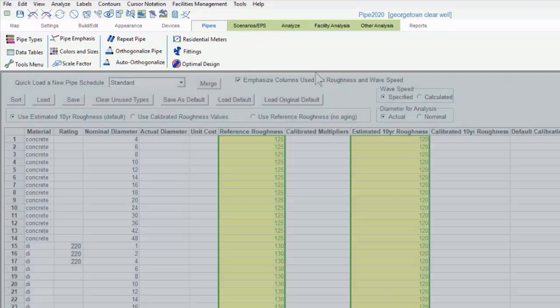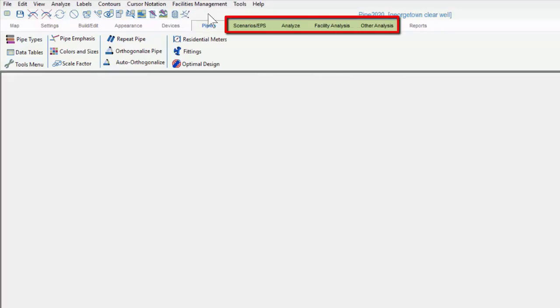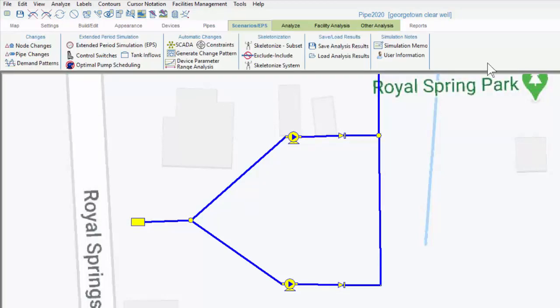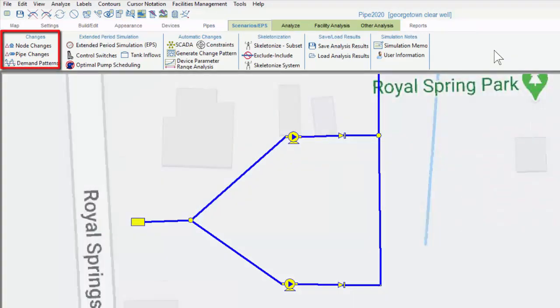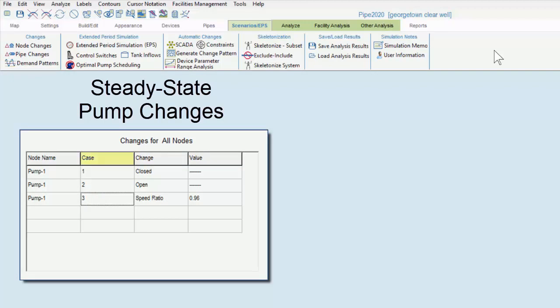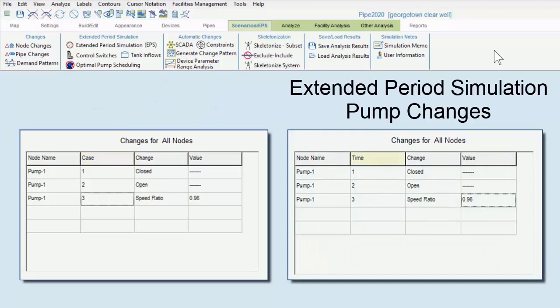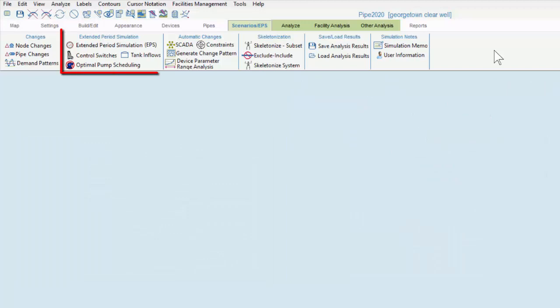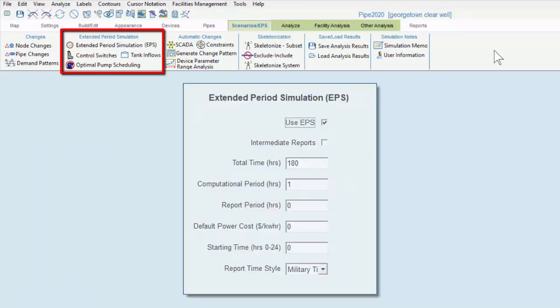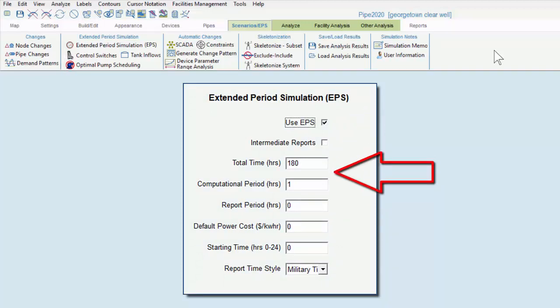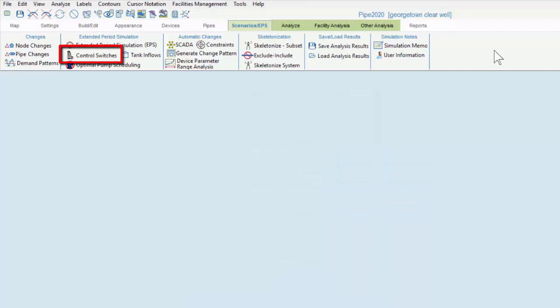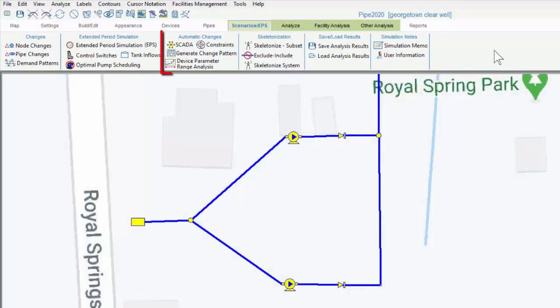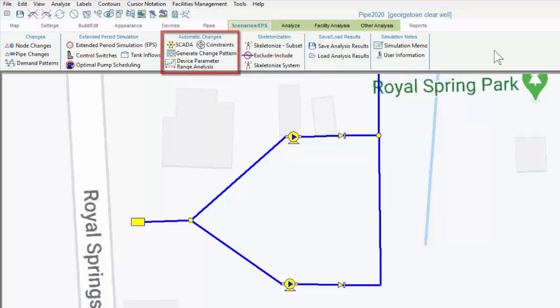The next four tabs are color-coded light green to distinguish them from the others since they allow us to set up and run different scenarios. Scenarios EPS is the first tab. Within it, the first submenu allows us to make changes to our model boundary conditions that can be applied for each case, for steady state scenarios, or for each time for extended period simulations. The next submenu only applies to extended period simulations. Here we can turn them on, set the duration of the simulation and the time step, as well as create control switches. For instance, if we want to turn a pump on to fill a tank based on a low water switching level within the tank, that's done here.